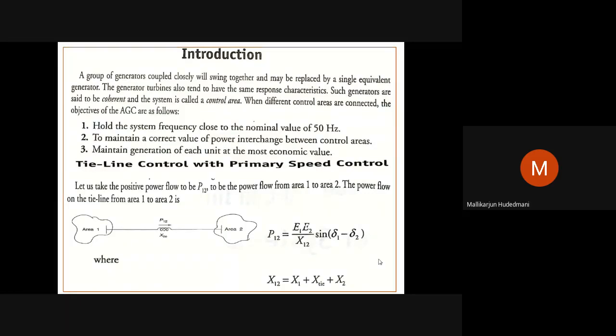Then they should have tie lines among them, and the AGCs of each area, A, B, C, D like that, should have a special feature and special role in the interconnected operation. That is, hold the system frequency close to the nominal value, whichever is specified. For us, if I say 50 hertz, all the interconnected areas should have AGCs with the objective to maintain the frequency very close to the steady state defined, like 50, and they should maintain the correct value of power interchange between control areas.